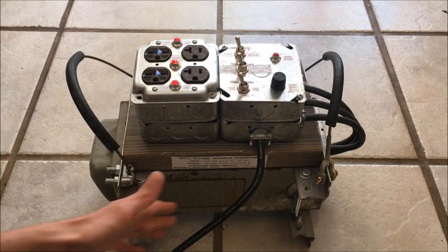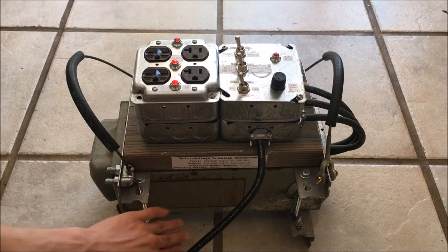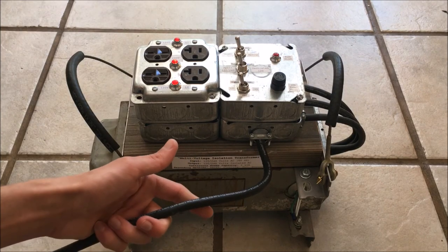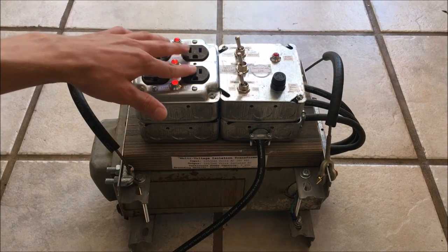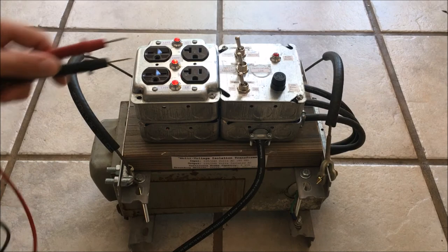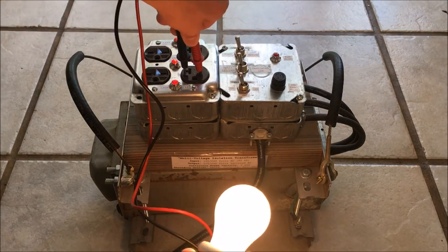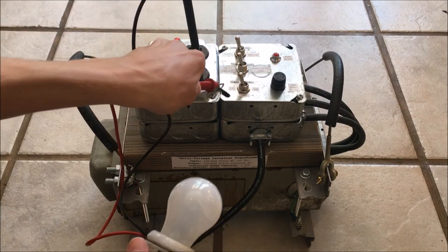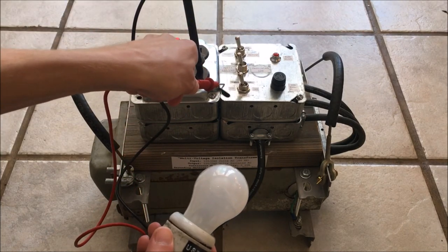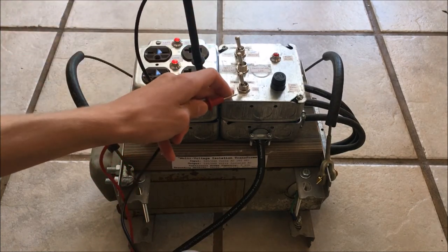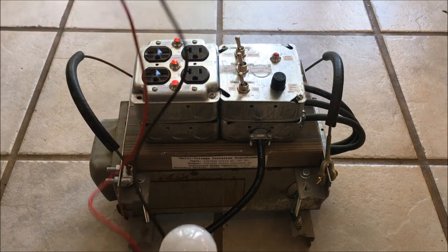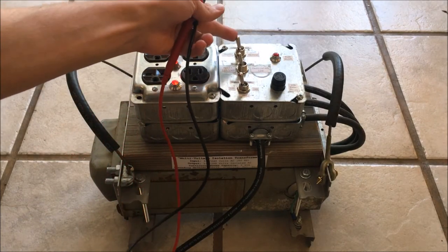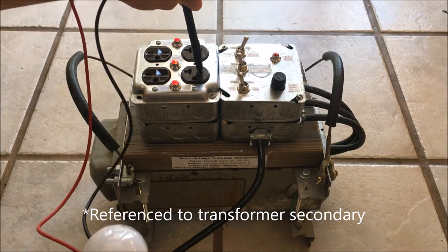What an isolation transformer does is it uses a transformer core which is an electromagnetic separator to keep the mains voltage coming in isolated from the mains voltage coming out. So when this is set on full isolation mode as you can see you get power from the output, however if I connect one side here to the hot and the other side to just the case of the transformer there's no current passing. In fact I could easily just put my finger here and touch the case and not worry about getting shocked either.